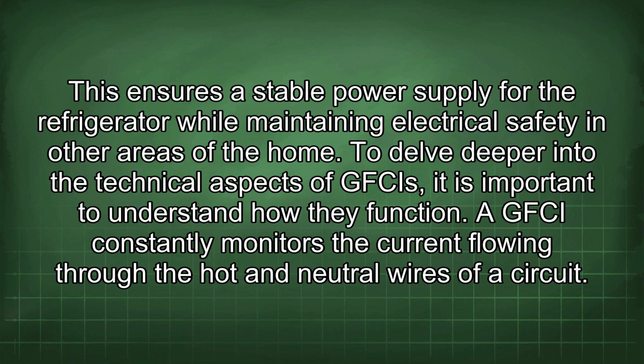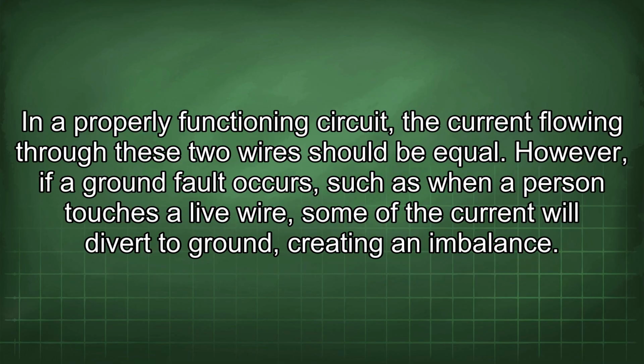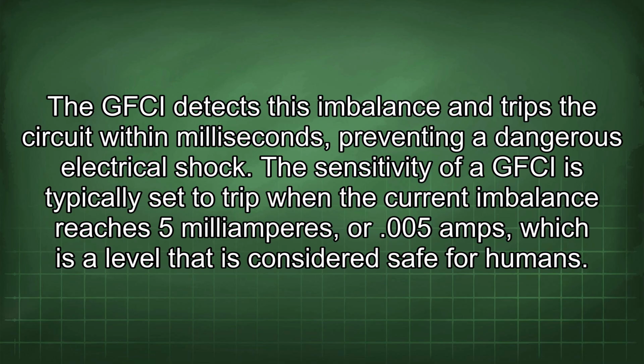To delve deeper into the technical aspects of GFCIs, it is important to understand how they function. A GFCI constantly monitors the current flowing through the hot and neutral wires of a circuit. In a properly functioning circuit, the current flowing through these two wires should be equal. However, if a ground fault occurs, such as when a person touches a live wire, some of the current will divert to ground, creating an imbalance. The GFCI detects this imbalance and trips the circuit within milliseconds, preventing a dangerous electrical shock. The sensitivity of a GFCI is typically set to trip when the current imbalance reaches 5 mA or .005 amps, which is a level that is considered safe for humans.